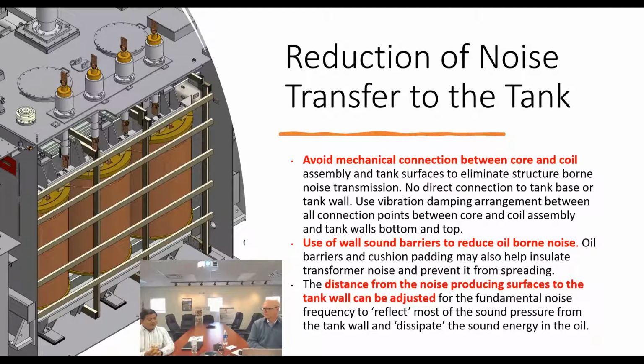The other way of doing it is to use the wall sound barrier to reduce the oil borne noise. So we can use the oil barrier or cushion padding inside the transformer tank, which will help to insulate the transformer's noise and prevent it from spreading outside. The distance from the noise producing surface to the tank wall can be adjusted for the fundamental noise frequency to reflect most of the sound pressure from the tank wall and dissipate the sound energy to the oil. And that is how, overall, we can isolate or reduce the noise transmitted from inside our transformer to the outside, or to the tank.